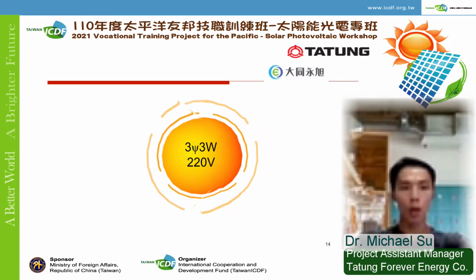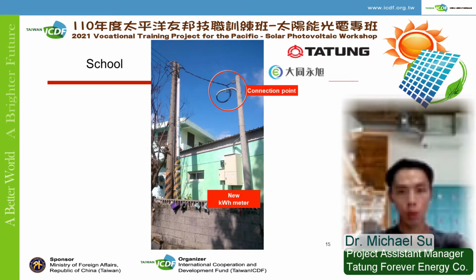Following up, I'm going to talk about the case of the 3-phase, 3-wire transformer which holds current of 220 volts. Usually, this kind of bigger transformer is for sites like schools or industrial areas. In this case, the cable comes from the high voltage public pole, the voltage is lowered, then transferred to another pole and the new meter we set up. The demarcation point is marked on the new pole for lower voltage. The side of the higher voltage pole is the responsibility of TPC. On the other hand, from the new pole to the meter is our zone of responsibility. This is the function and purpose of the demarcation point.